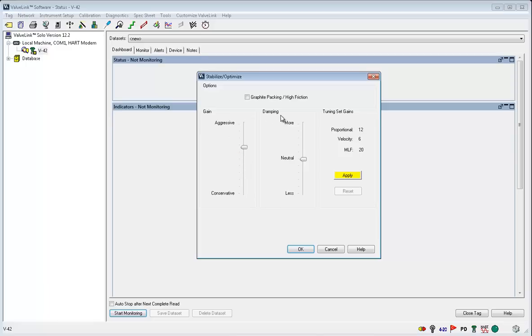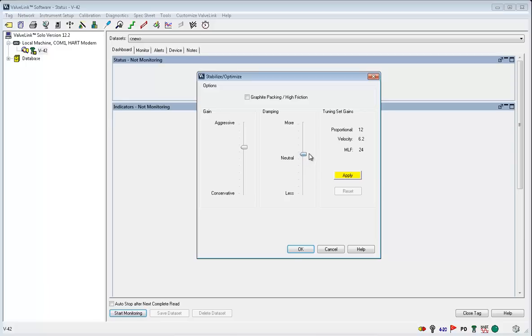Changing the damping changes the velocity and the minor loop feedback but not the proportional values. The damping slider aids in stabilizing the system when high gains are used.